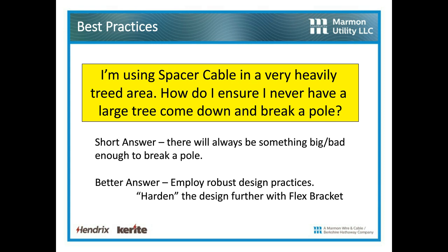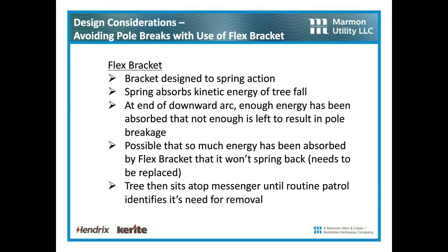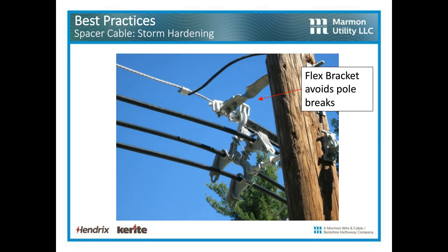A flex bracket is something we came out with. The bracket is designed with spring action. The spring absorbs the kinetic energy of a tree fall at the end of the downward arc. Enough energy has been absorbed by that bracket that not enough energy is left to result in the pole break. It's absorbing that energy on the downward thrust of that tree hitting the messenger. It's possible that so much energy has been absorbed by the flex bracket that it won't flex back. Fair enough, it's going to have to be replaced, but then the tree is just going to sit on top of the messenger until a routine or an annual patrol identifies its need for removal. And this is what that flex bracket looks like.